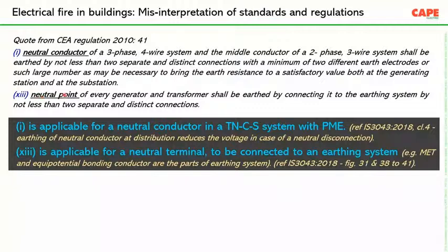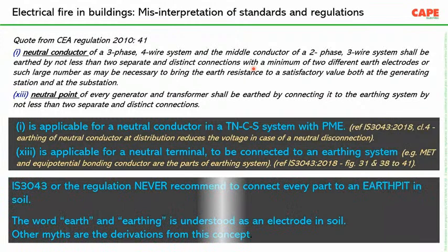Then the next one: the neutral point of every generator and transformer shall be earthed by connecting it to the earthing system by not less than 2 separate and distinct connections. Please understand, this is the earthing system. It is not an earthing electrode. The earthing system consists of earth bus bar, earth conductor, equipotential bonding conductor, earth electrode. So the earthing system is a combination of several things. So basically what I wanted to tell you is the regulation never has written that a transformer neutral has to be connected to an earth electrode in soil, and the transformer body separately, 2 numbers. This is never written in the standard and it's wrong.